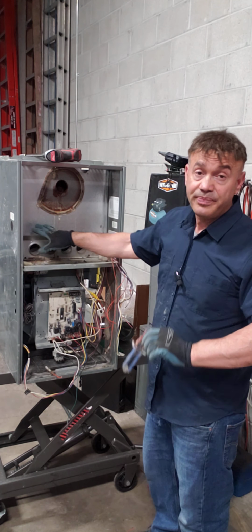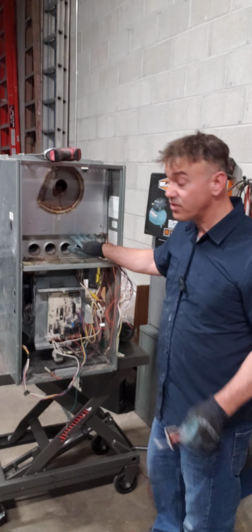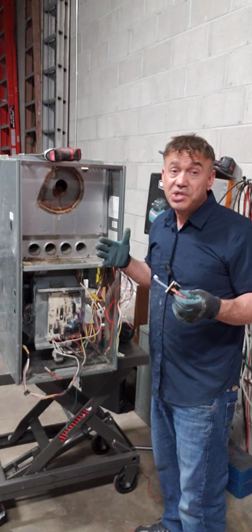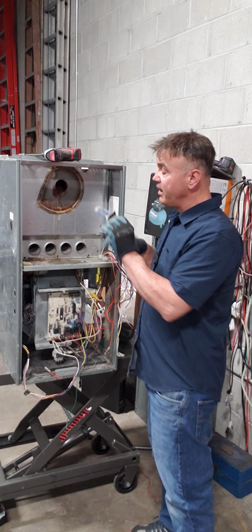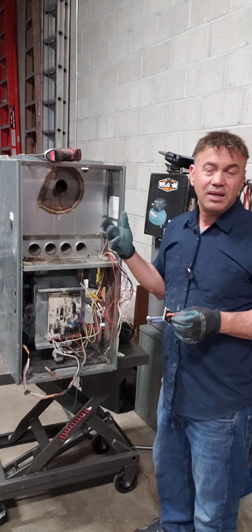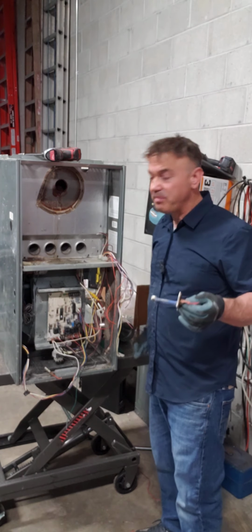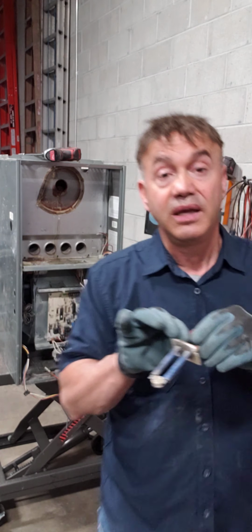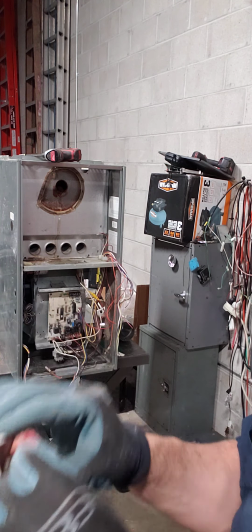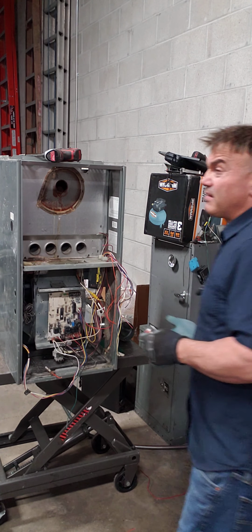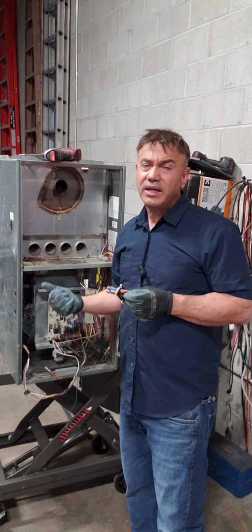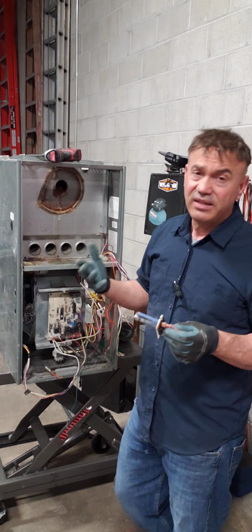Basically, this is the limit. The rollout switches monitor the temperature of the burner compartment. This one monitors the fresh air intake coming in and out. If the filter is dirty, or something is stuck in the blower, a lot of times shopping bags can be sucked into it. This guy has to monitor the temperature of the heat exchanger. So for example, it says L170, right? L170 minus 20. So L170, the cut-in minus cut-off, usually it tells you the cut-off.